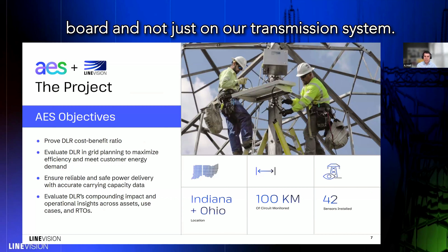First, we wanted to prove the cost-benefit ratio: what is the cost and time to deploy this technology, and then what are the benefits for AES and our customers? Some of those benefit streams include capacity gains from DLR, but as we'll talk about in further slides, it's not just about percent capacity gains over static or ambient adjusted ratings. It's really about better visibility into how these critical assets operate, allowing you to safely and reliably operate lines, as well as smartly plan the grid with data that grid planners and operators don't have without deploying dynamic line ratings.